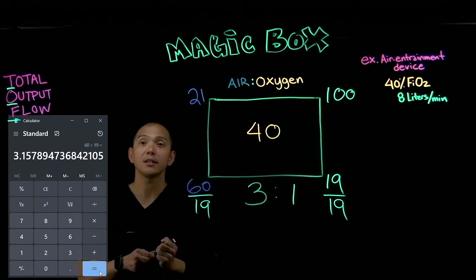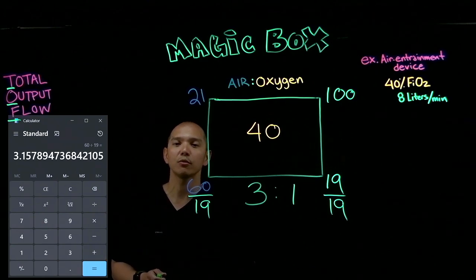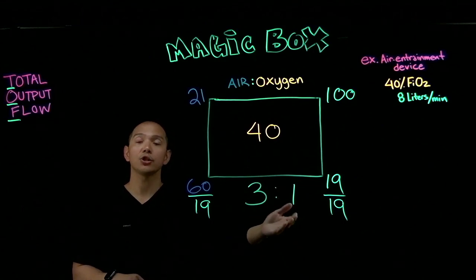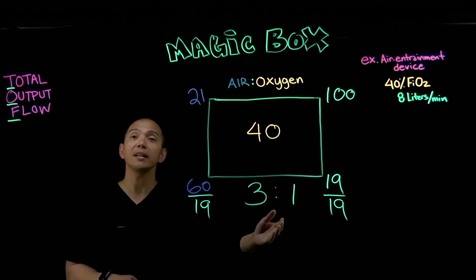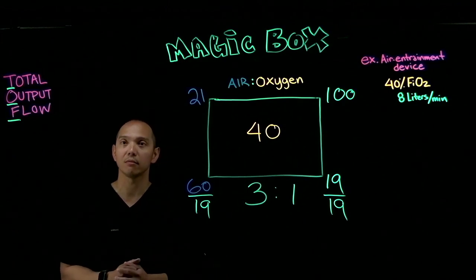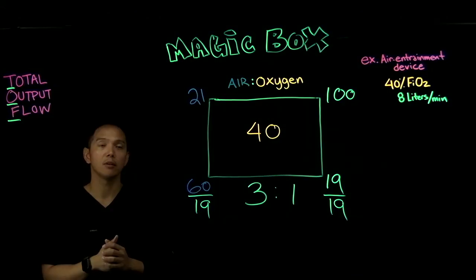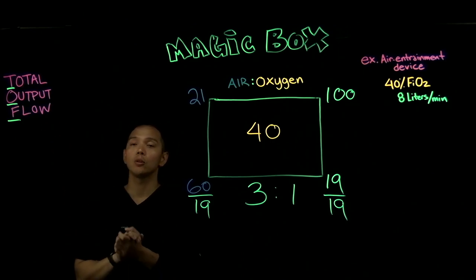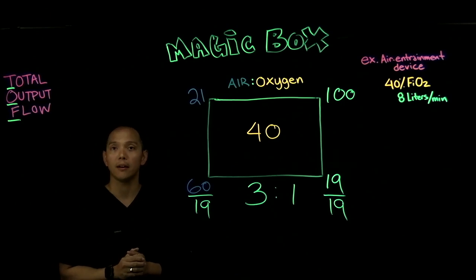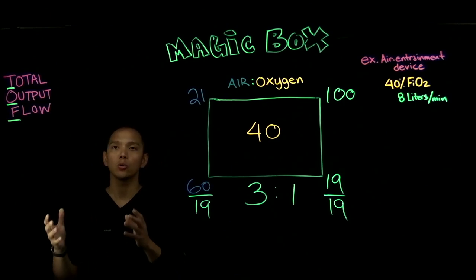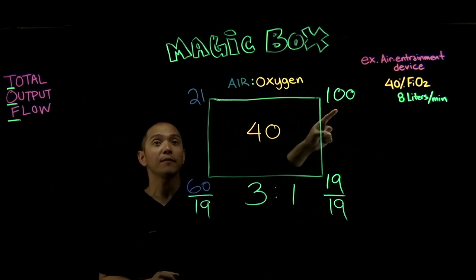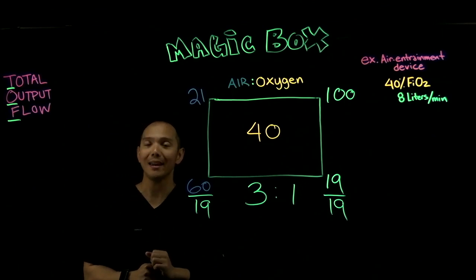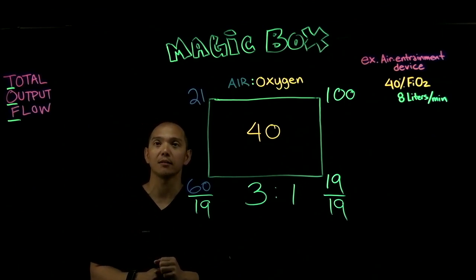This is the air-to-oxygen ratio: for every one part of oxygen, we are entraining three parts of room air — a 3:1 ratio. Now we're going to talk about the total output flow, or TOF — the total output flow from this air entrainment device set at 40% FiO2 with the flow meter dialed to 8 liters per minute.